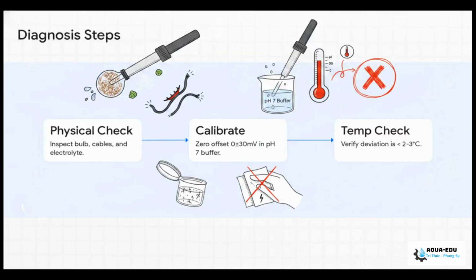Assuming it's an error, step 2 is getting hands-on with a physical check. Safely pull the probe out, but hey, make sure you lock out the automated controls first, right? Check the glass bulb itself. Is it totally coated in brown oil, maybe white calcium scale, or even green algae? Check the cables for rat bites or loose connections. Is the reference electrolyte completely dry?